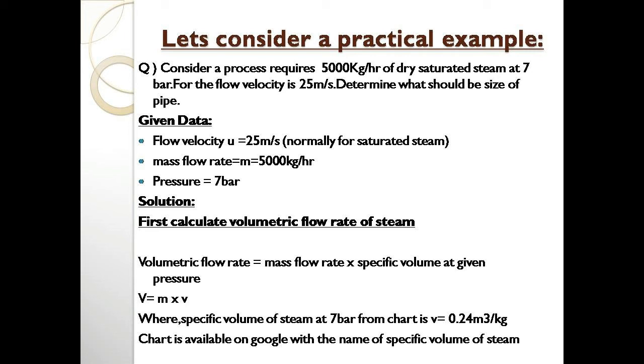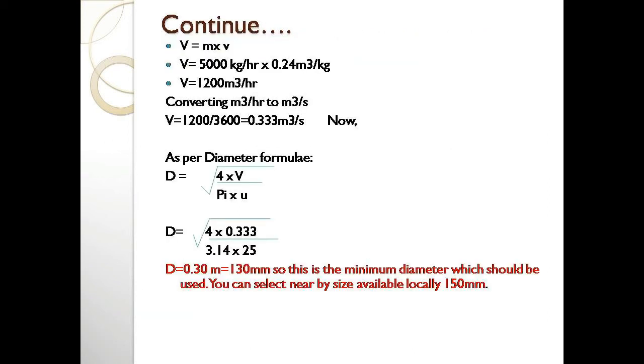So V equals m multiplied by specific volume (v). The specific volume of steam at 7 bar, taken from a steam table chart (easily available on Google), is 0.24 m³/kg — meaning each kg of steam occupies 0.24 m³. Therefore, volumetric flow rate = 5000 kg/hr × 0.24 m³/kg = 1200 m³/hr.